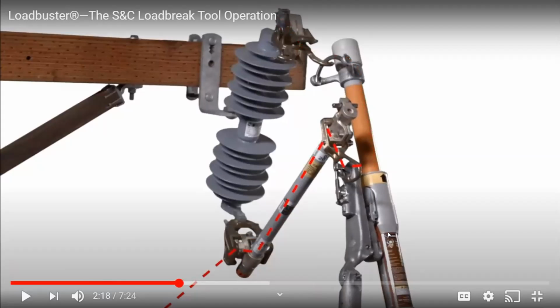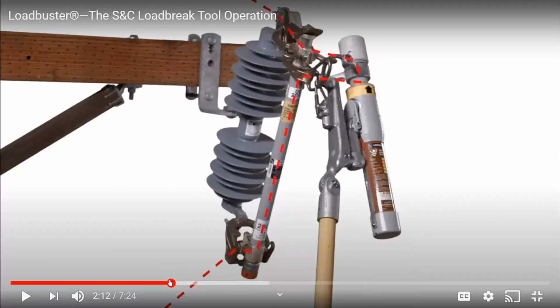Okay, these things are meant to be operated. Load busting's happening in this tube right here. And actually in some cases, there's an exhaust system here at the bottom. You'll see a little bit of smoke and fire fly out of the bottom because it's busted a large amount of load. You want to operate that thing like I've told you guys, the way you put on elbows and pull off elbows in a pad mount transformer. Smooth and quick, so that the load busting operation goes on in here and does what it's meant to do, break load quickly. If you lollygag around about it, it's going to start arcing in this tube and the load's not going to bust.